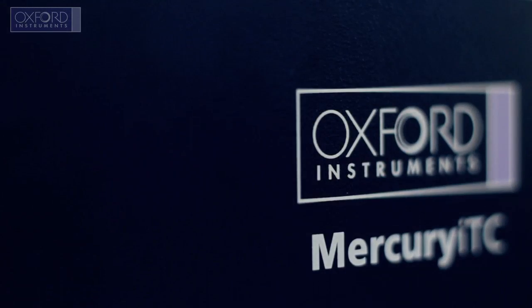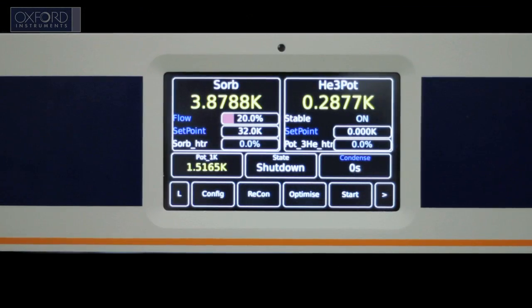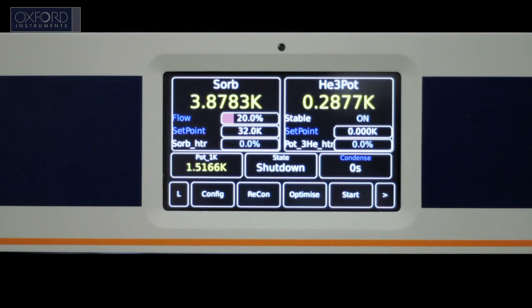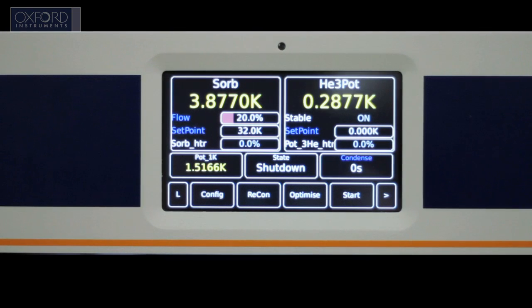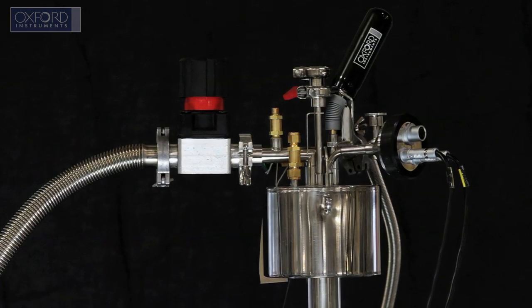The Mercury ITC also has a number of custom control modes. In the example, the Heliox mode is used to control a single-shot helium-3 insert.